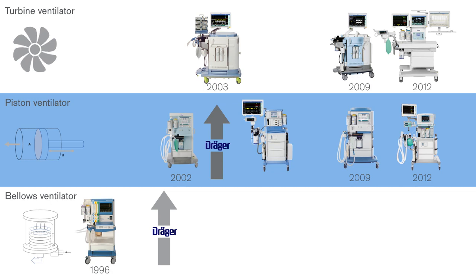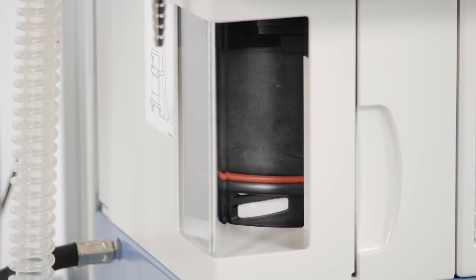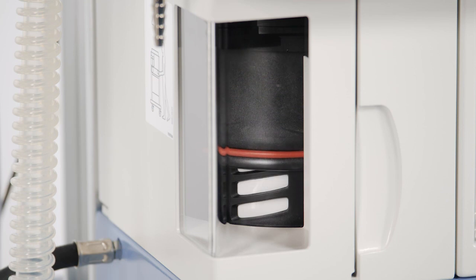as the piston offers several advantages. The piston runs on electricity and does not require any gas to drive the ventilator. Therefore, a piston ventilator consumes significantly less gas compared to a bellows-driven ventilator during operation.